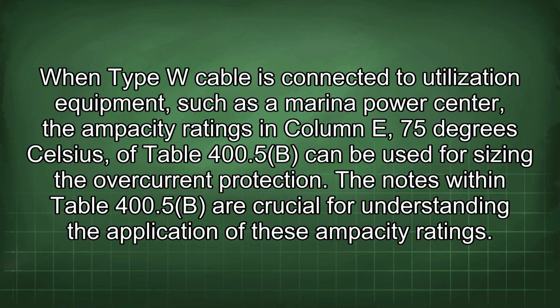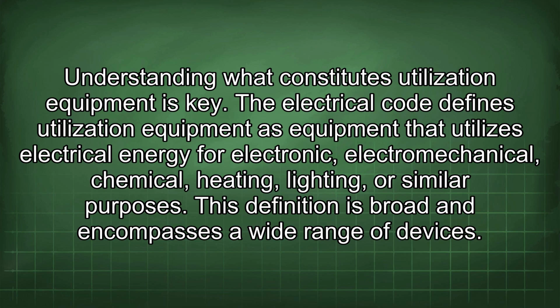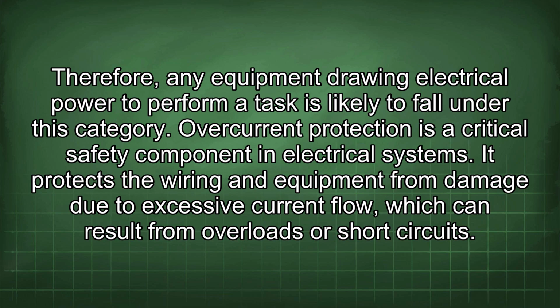When Type W cable is connected to utilization equipment, such as a marina power center, the ampacity ratings in column E, 75 degrees Celsius, of Table 400.5b can be used for sizing the overcurrent protection. The notes within Table 400.5b are crucial for understanding the application of these ampacity ratings. Understanding what constitutes utilization equipment is key. The electrical code defines utilization equipment as equipment that utilizes electrical energy for electronic, electromechanical, chemical, heating, lighting, or similar purposes. This definition is broad and encompasses a wide range of devices. Therefore, any equipment drawing electrical power to perform a task is likely to fall under this category.